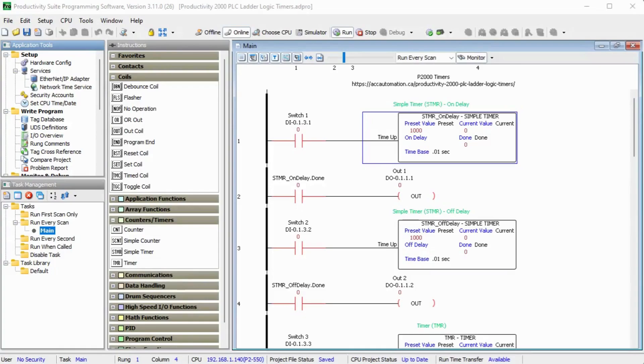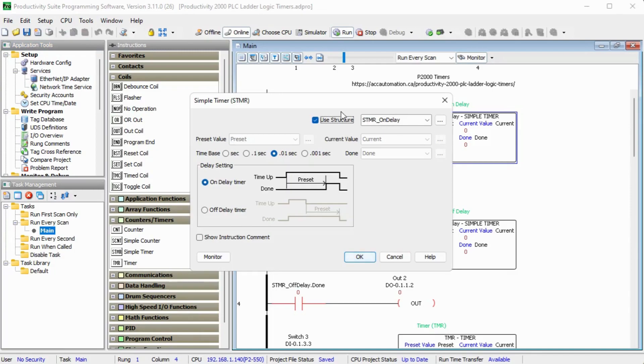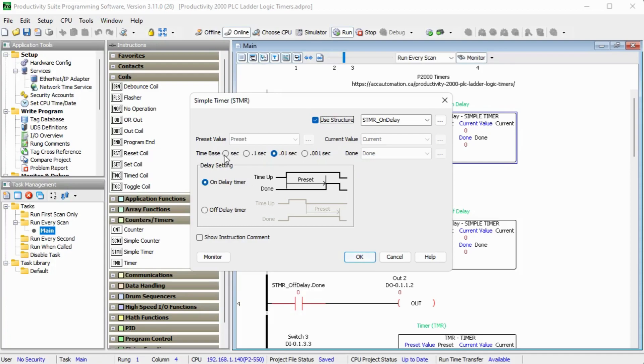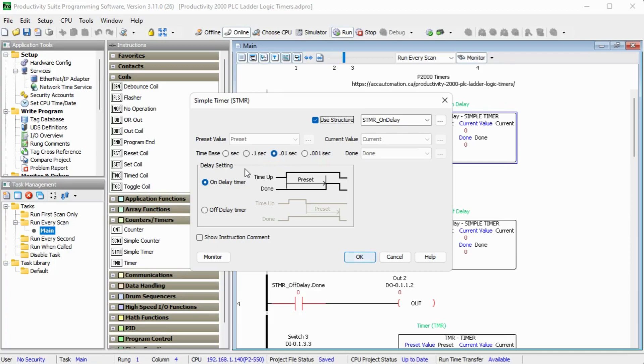We will first use the Simple Timer, STMR, as an on-delay timer. So looking at my program here, I am connected online to the PLC. If I double click on this, I can see the instruction itself. And you will see that we're using a structure called STMR underscore on-delay. And that sets up my present value, my current value, and my done bit. And I also have selected the time base rate of 0.01 seconds. And we're going to set the preset value to 1000, which will be 1000 times 0.01 seconds, which gives me 10 seconds. You can see that this instruction also shows you the delay setting and the timing chart right on the instruction itself. In this case here, we're going to have selected the on-delay timer.